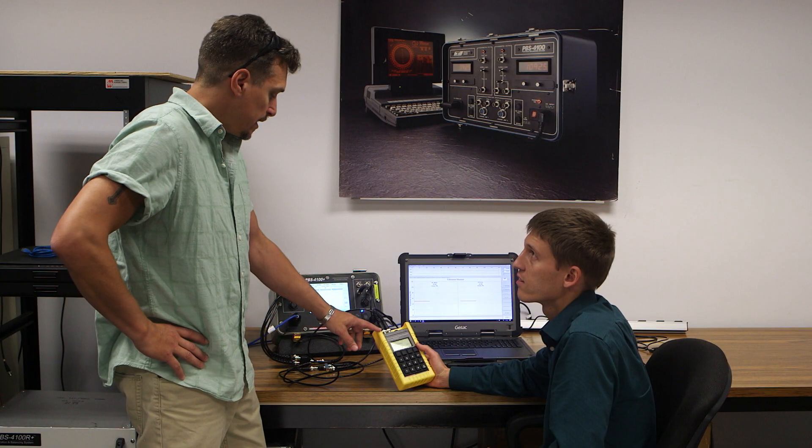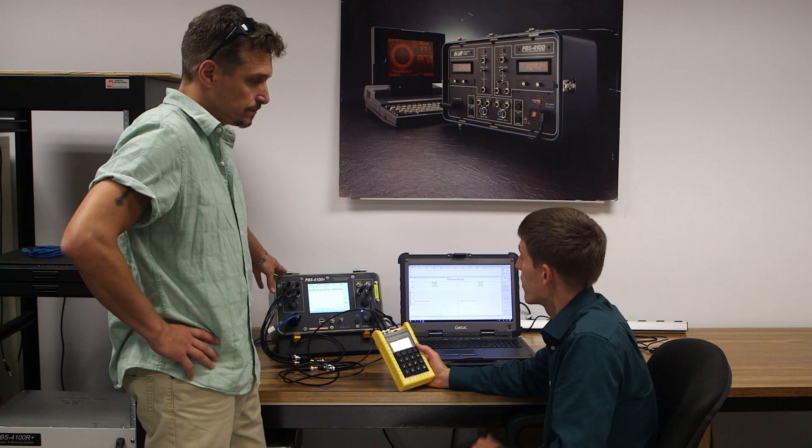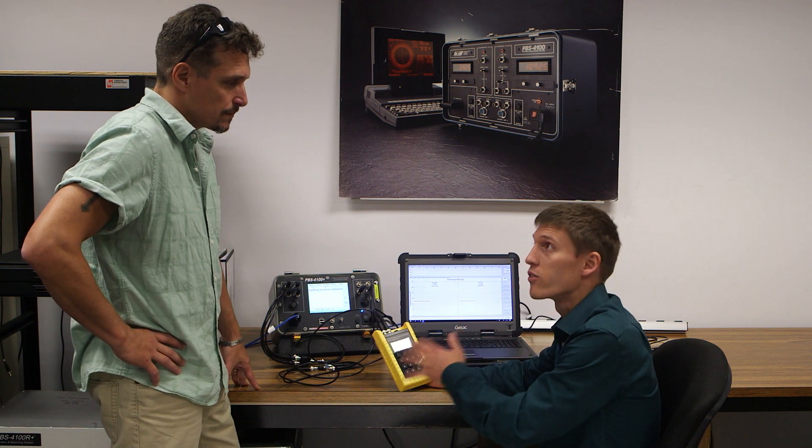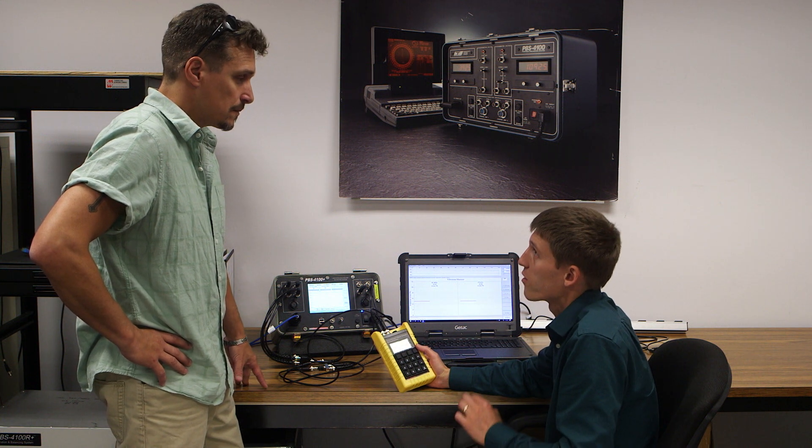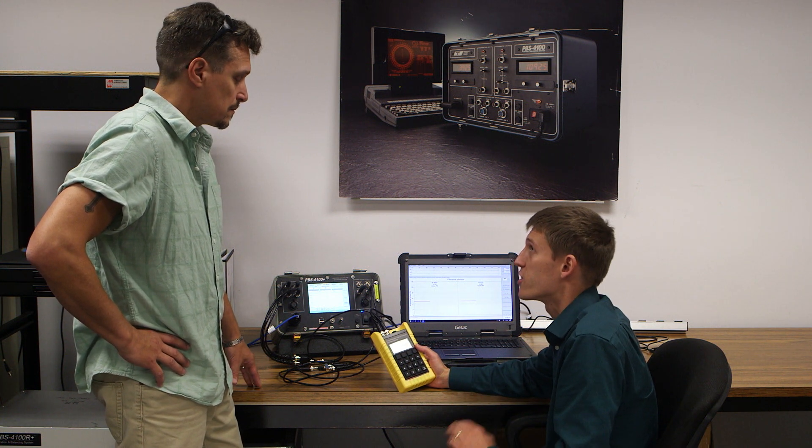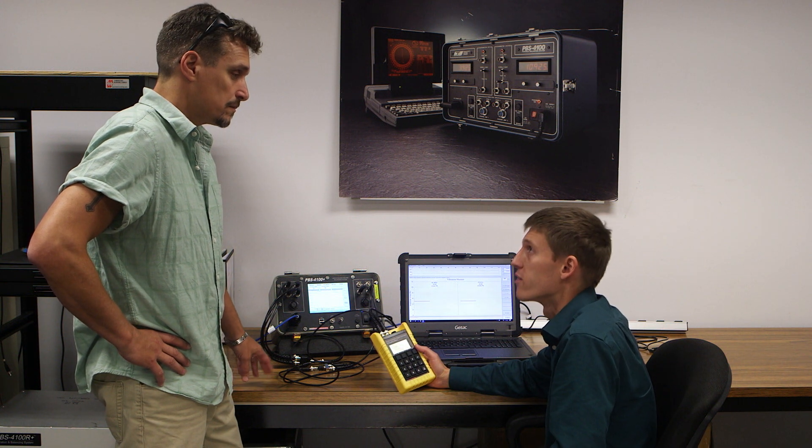Why would we use the 1510A to calibrate our PBS4100? Over time the electronics in the equipment is going to drift. Just a little bit, but if you really rely on precise, accurate signals, you need to check those signals every 6 to 12 months to make sure they're operating within specifications.